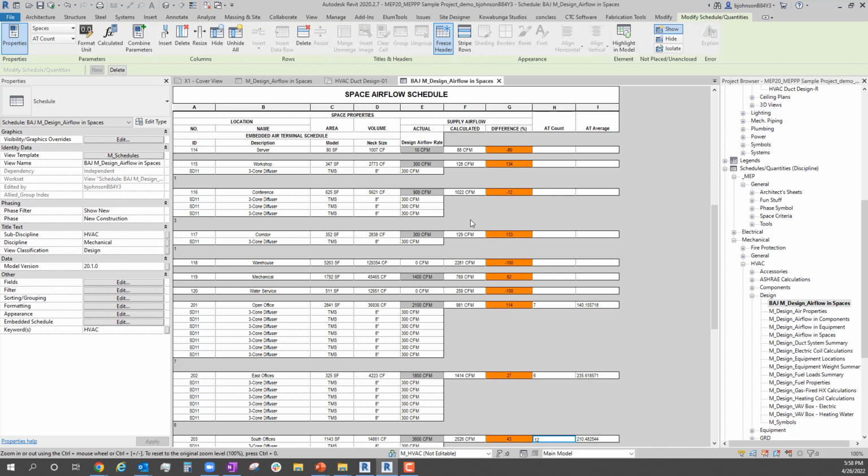So in those cases, I can't help you with those, right? But on really good architects, they have a really good idea of their designs, their sizes, and everything else, and they're not going to continually change the buildings over and over and over again. This is a very solid workflow, in my opinion, to be able to place those items once, do heating and cooling loads, change the values once, and then draw duct. Because if I were to come in here and say this is the reverse, I had 150 in there, but they have to be 300s.